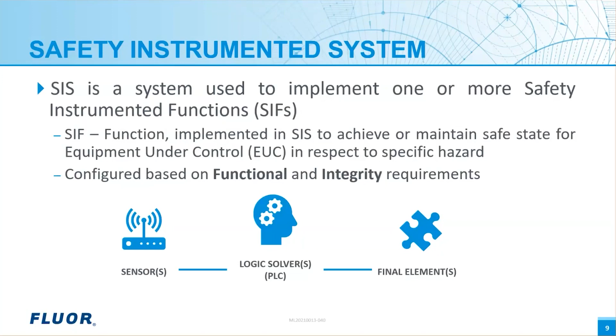From our previous example, for the high-level SIF in the tank, it can be SIL 2 or SIL 3, depending on the risk associated with the overfill scenario. IEC 61511 is the main standard referred to when we talk about SIS in the process industry. It provides the life cycle approach, as you can see in the slide, for the design and the operation of the SIS. So basically, the SIS life cycle is all about the journey undertaken from SIS design to operation with an endeavor to achieve process safety.